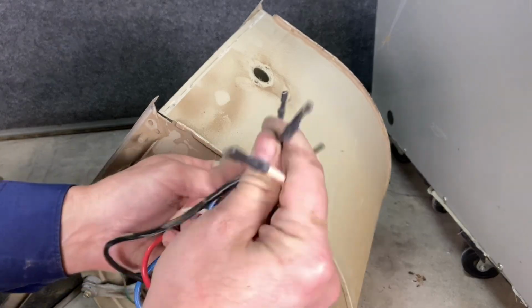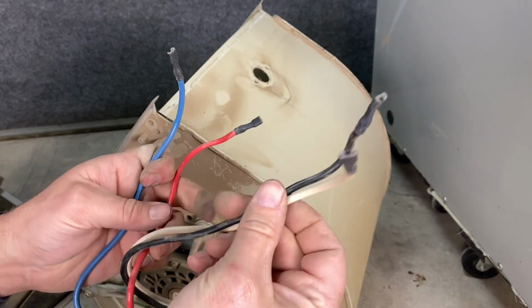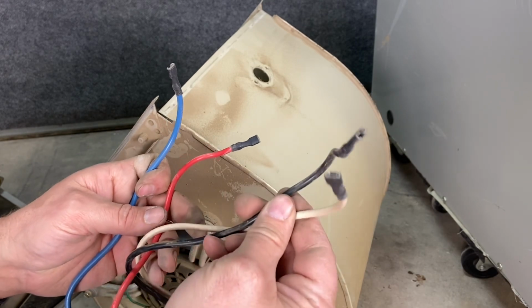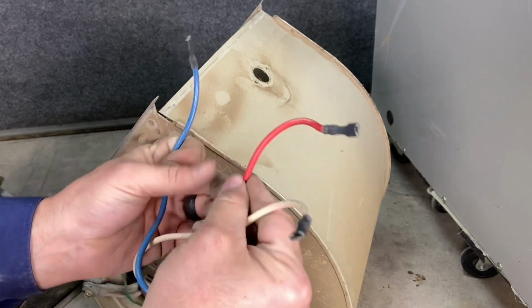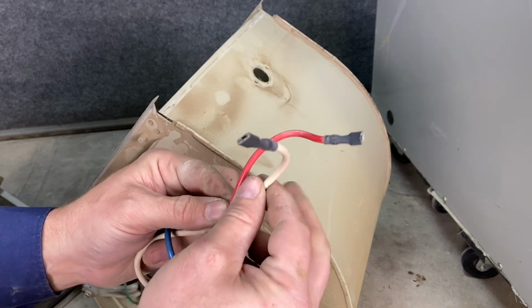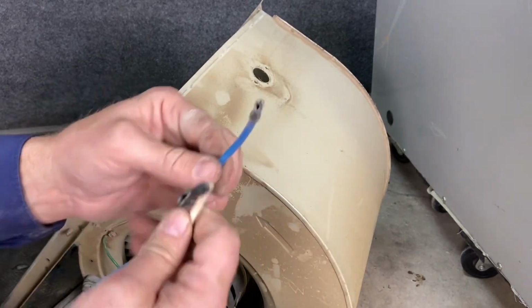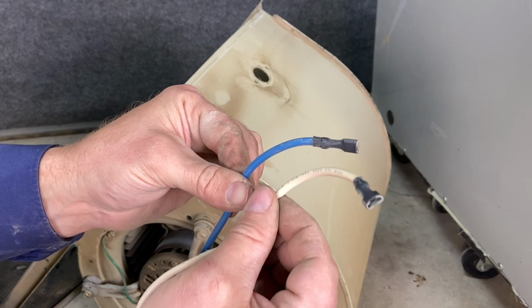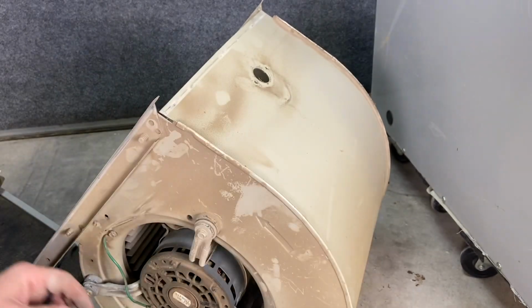So it's going to be, for example, black for high speed and neutral, which is the white, or red for low speed and neutral, which is the white, or we would have blue for medium speed with the neutral, which is white. So 2, 2, and 2 all the way around.